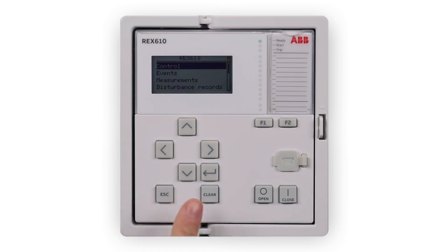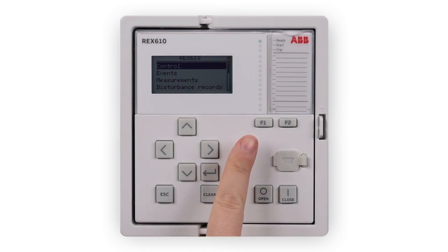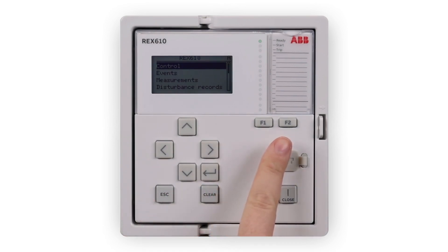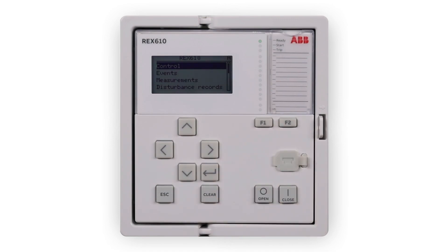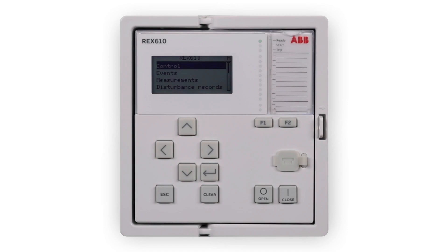REX610 has two freely programmable function keys, F1 and F2. The functionality can be freely programmed with the application configuration tool of PCM600. The LHMI includes three protection indicators in the upper right corner: Ready, Start and Trip. There are also 10 programmable LEDs on the front of the LHMI. These LEDs can be configured with PCM600 and the operation mode can be selected with the LHMI or PCM600.